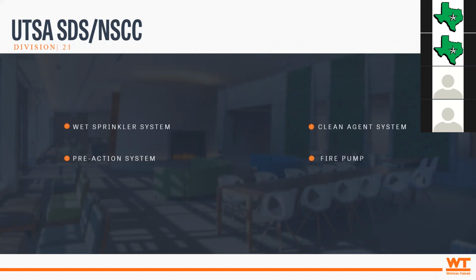In fire protection, we've got a fully sprinkled building, except for our area that has a pre-action system and a clean agent system, inside of a data center. Everybody can imagine why we don't really want a wet sprinkler system in that area.